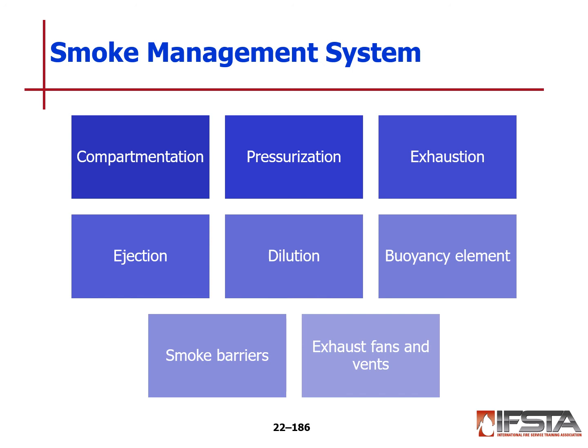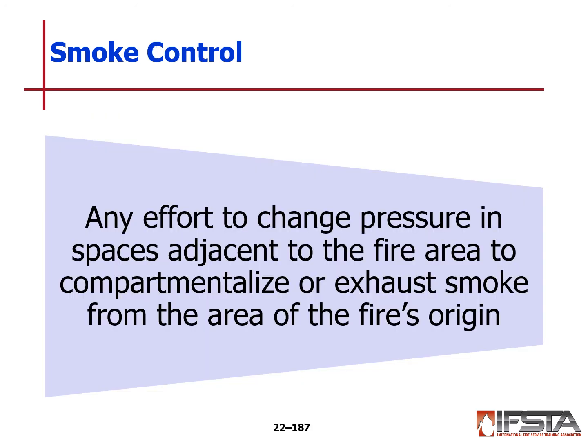There also may be smoke barriers installed, and exhaust fans and vents pre-installed into the building and the system. And this all will help us either move smoke, remove smoke, or pressurize in areas that we may need it. Any effort to change the pressure in spaces adjacent to the fire area to help compartmentalize or exhaust smoke from the area of its original origin is called controlling smoke.